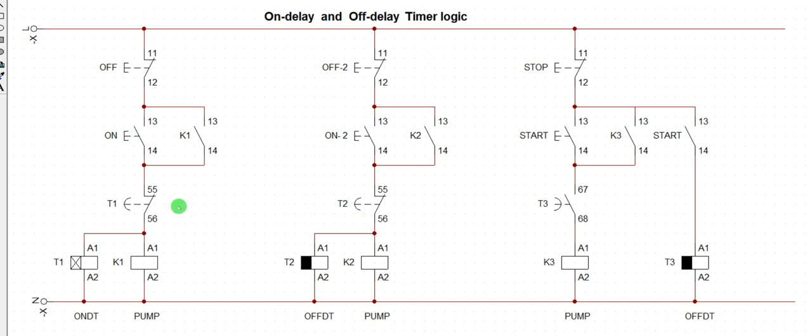But with an on delay timer, when that transition time is complete, the equipment will shut down, but the power will still be maintained to the on delay timer. That is the difference between on delay and off delay. When off delay shuts down, the logic completely goes off. The signal of the power goes off. But an on delay timer will maintain the signal to the logic, and it will shut down the equipment, but the signal to the relay will still be on. So that is the difference between the two.